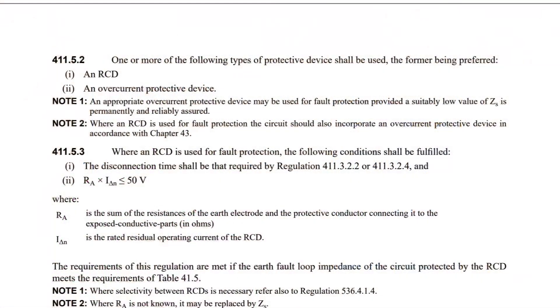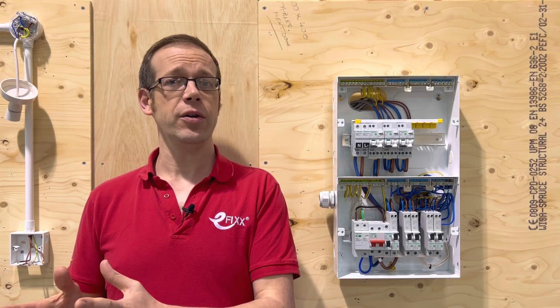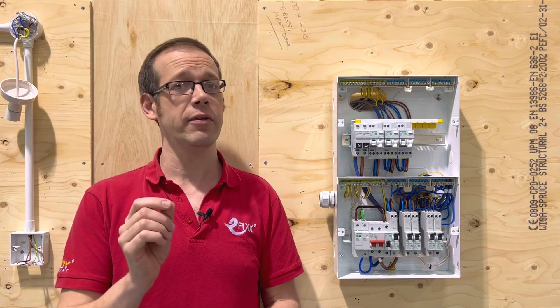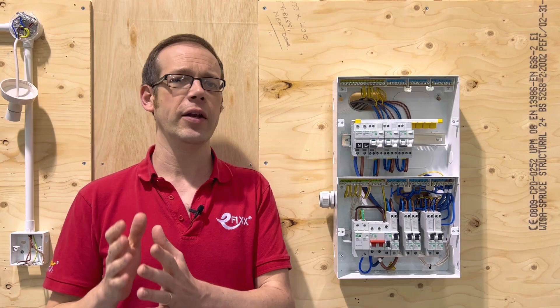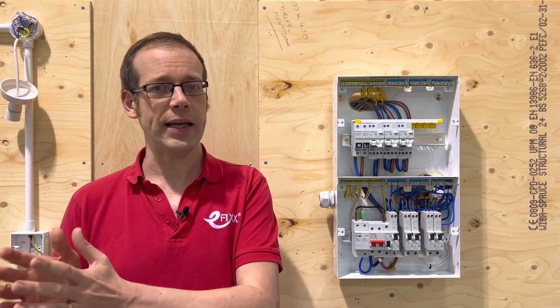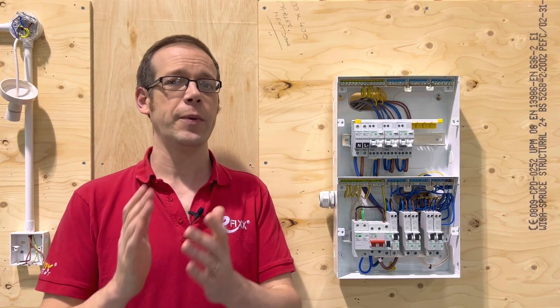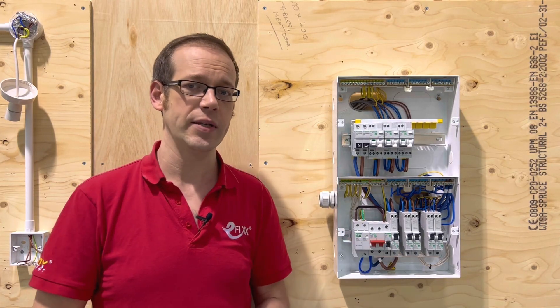It's worth noting regulation 411.5.2 which states for a TT system one or more of the following types of protective device shall be used, the former being preferred. Number one an RCD, number two an overcurrent protective device. So according to indent 2 you can get away with using an MCB as long as you meet the requirement in note 1 which says an appropriate overcurrent protective device may be used for fault protection provided a suitably low value of Zs is permanently and reliably assured. In practice it's very hard in a TT arrangement to get a low enough value of Zs to let you use an MCB and so RCDs are usually the way to go especially as they're likely to be required for additional protection as well.